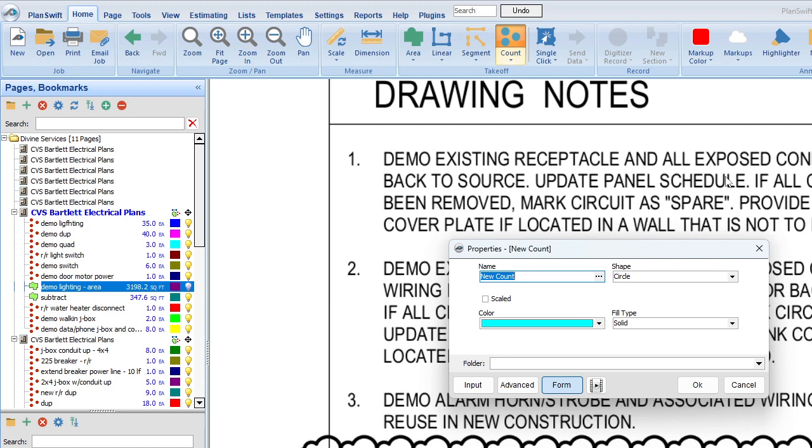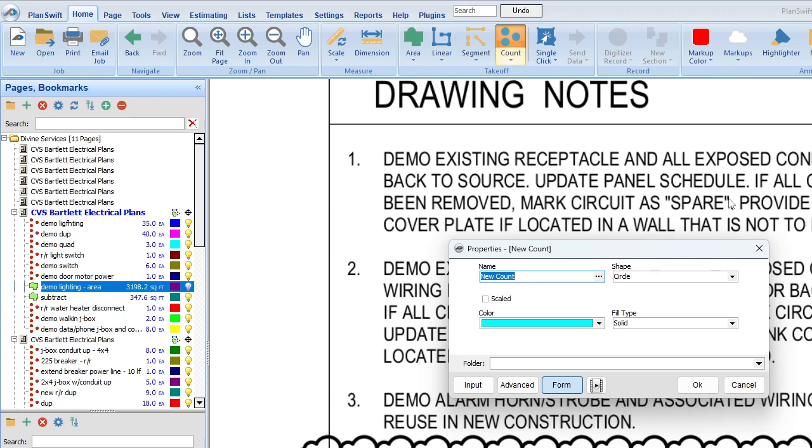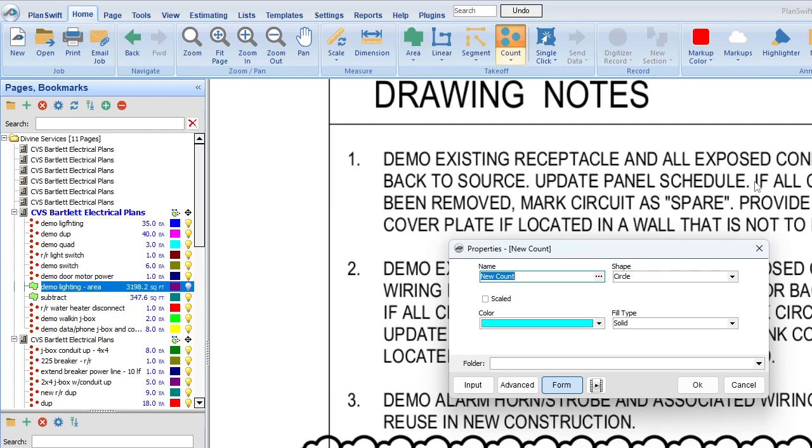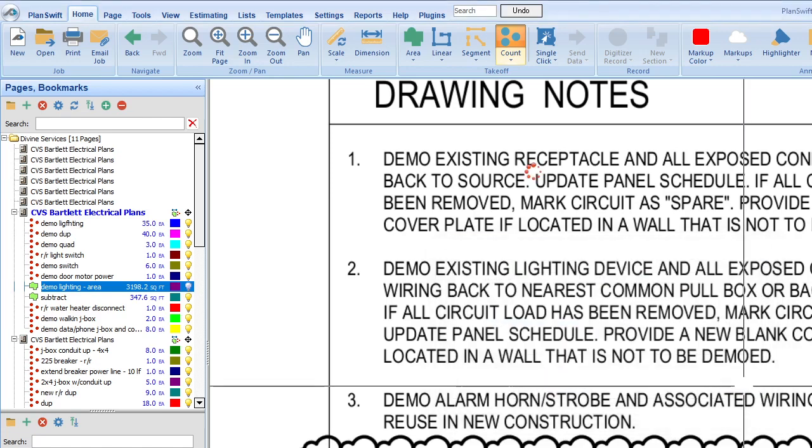Update the panel schedule - if you're new, you may want to do that, but rule of thumb for me is when we have a renovation, we do what's called balance the panel. So we give time for replacing all of the breakers that are there, reconfiguring the breakers. So it depends on the size of the panel. That includes updating the panel schedule, so I don't need to count for this in this case. But that's something you want to think about from my years of doing this.